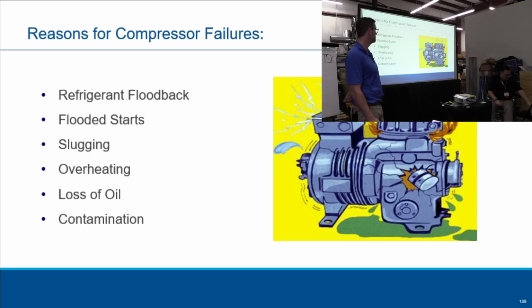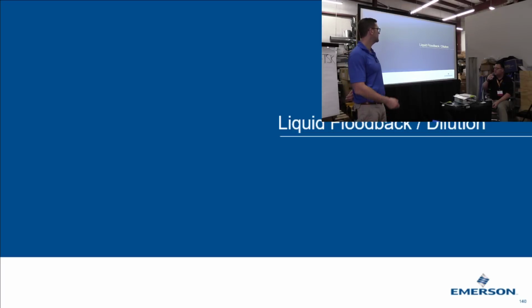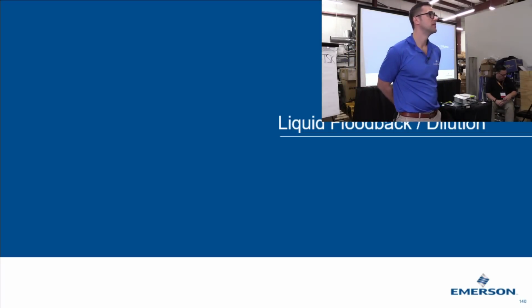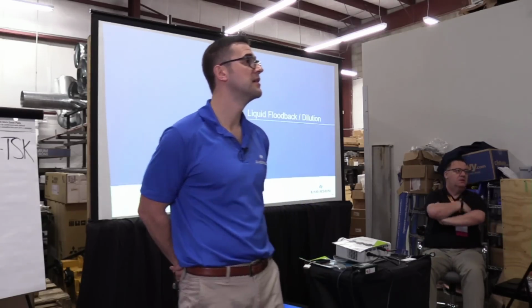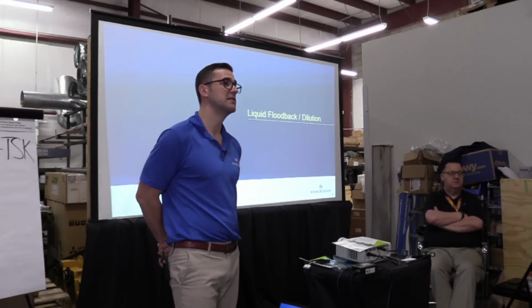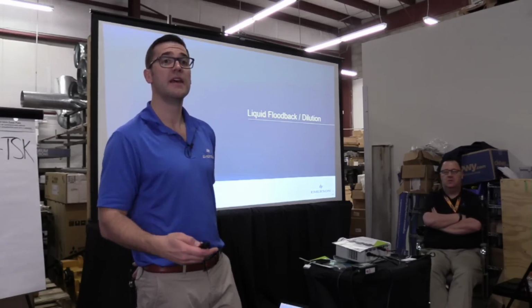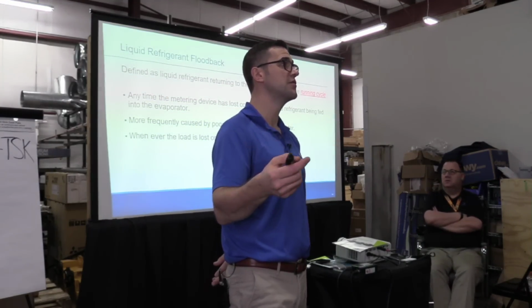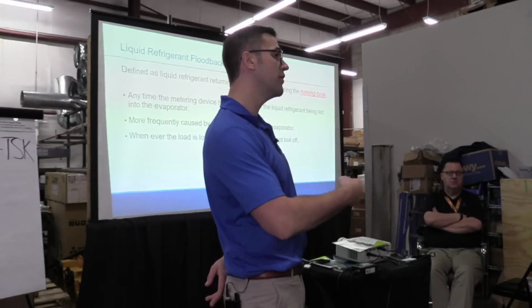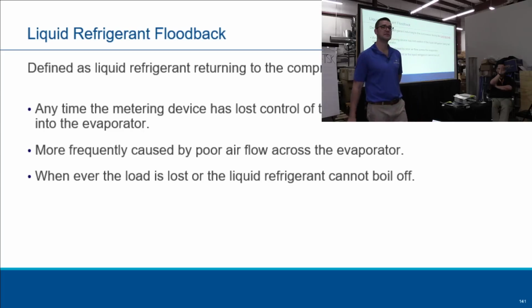Okay, what's liquid flood back? We have liquid refrigerant coming back to the suction. And how does that happen? Low superheat. Exactly. The compressor's running, no superheat, and liquid returns to the compressor while it's running. That's flood back, or liquid dilution.